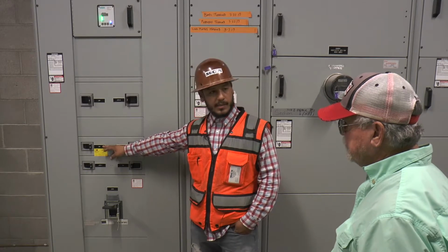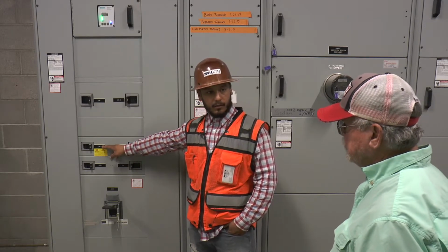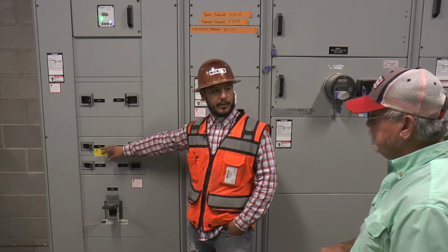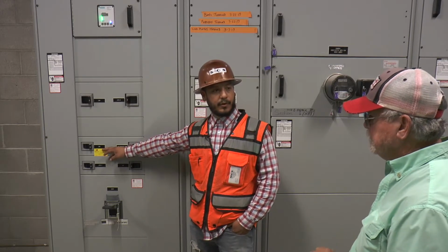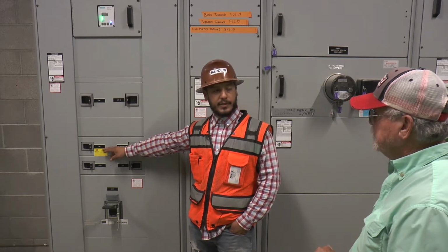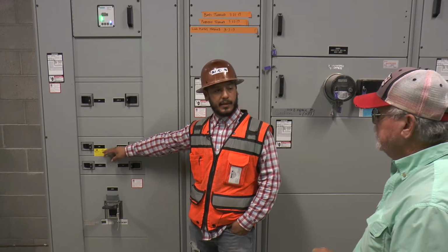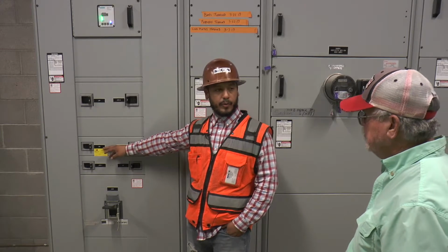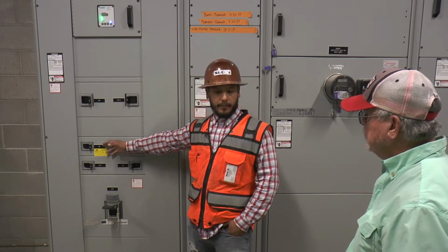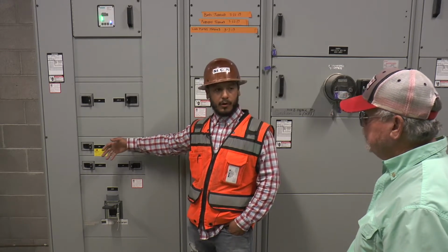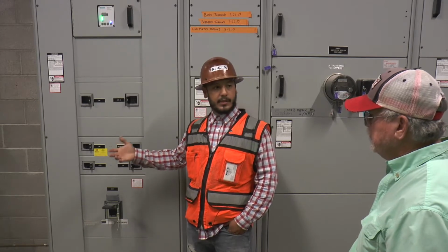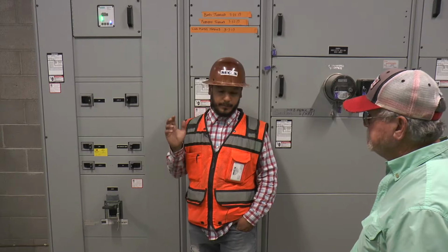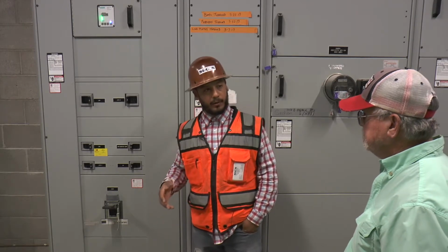9H1 is level 9, which also is high volt 480 going up, but stepping down to another 75 kVA transformer, which feeds levels 13, 16, 19, 22, 25, and 28, which are all low volt panels fed through the transformer for all the same common areas, exhaust fans, lighting, all in the common area, and that is just normal power.